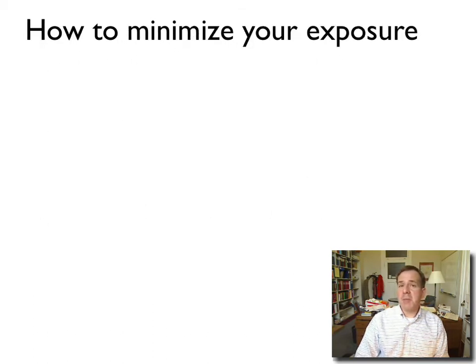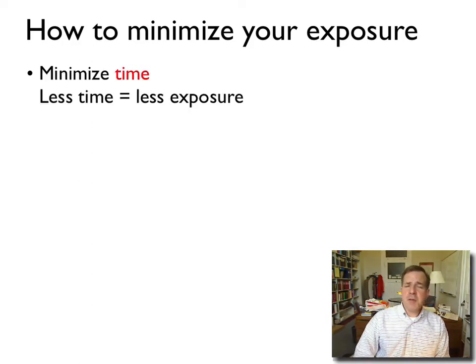Well, there are basically three basic principles. The first is time. We try to minimize the time that we spend working with or near radiation-producing equipment, and relatively obviously, less time equals less exposure. For instance, if you are setting up a diffraction scan in the diffractometer down in the X-ray lab, rather than spending the 2 hours that it takes your scan to run sitting there on the computer surfing the web, you should just leave the room. That way, even though the chance of you being exposed to some radiation in that room is small, you basically eliminate that risk if you simply leave the room.